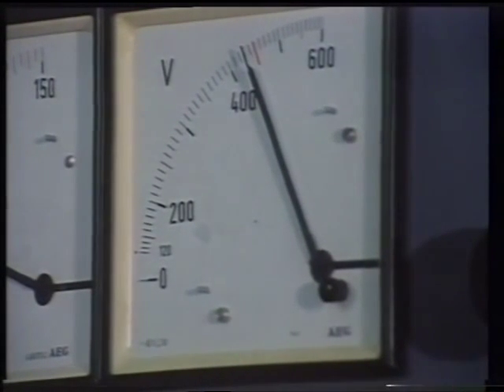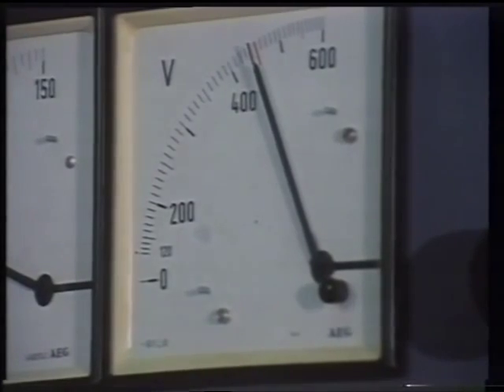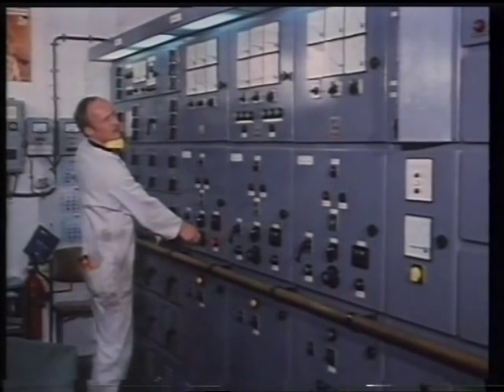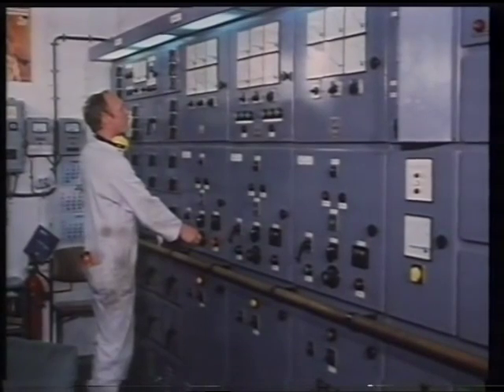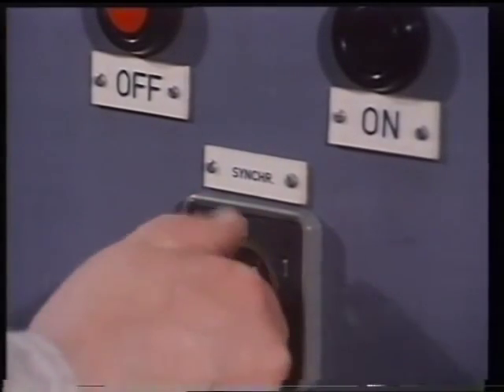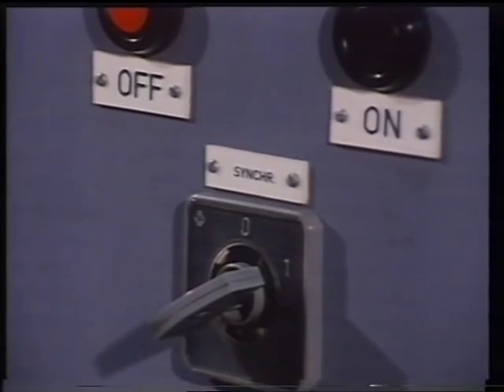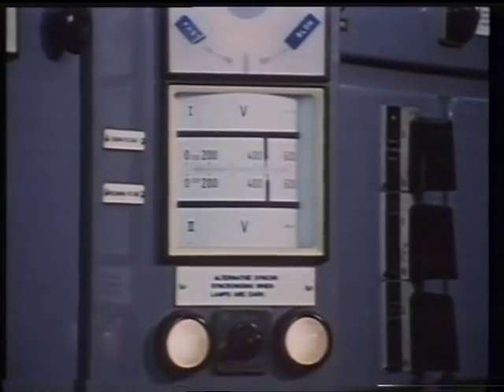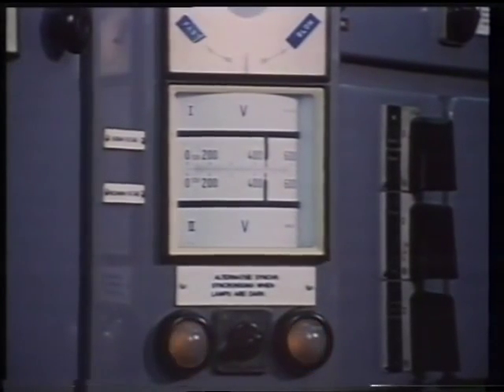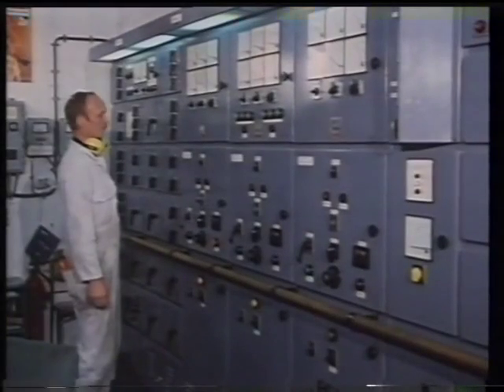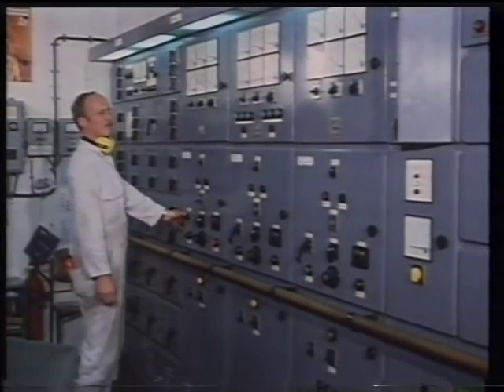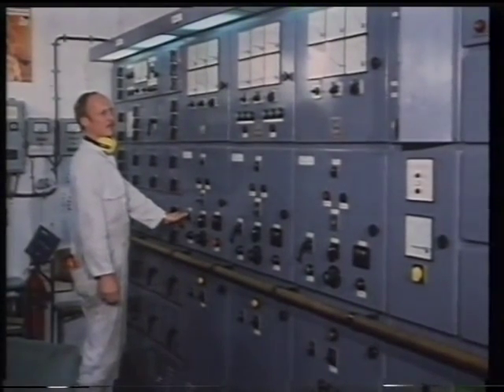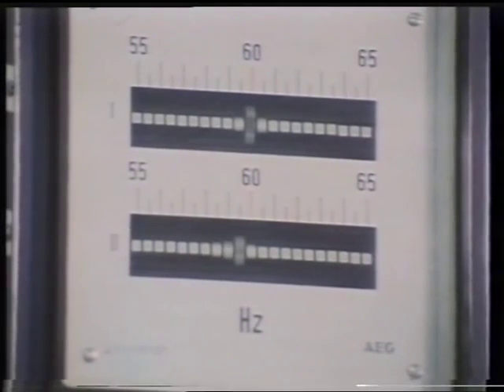Being an AC system, the voltage, the frequency and the phases of the incoming supply have to be identical with those on the bus bars before the incoming alternator circuit breaker can be closed. When the required voltage is reached, a synchroscope is switched in. A synchroscope and phase indicator lamps show the phase shift between the two supplies. The speed of the incoming alternator is further increased for the output to reach the required frequency. In our case, 60 cycles per second.